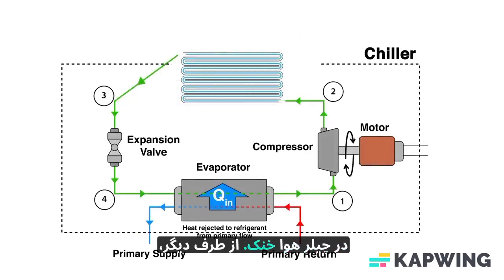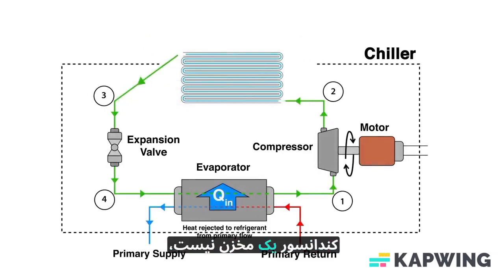In an air-cooled chiller, on the other hand, the condenser is not a tank, but instead a series of coils containing the refrigerant. In this case, the chiller is stationed outside. The unit's fan pulls ambient air over the coils, which cools down the refrigerant before it reaches the expansion valve.